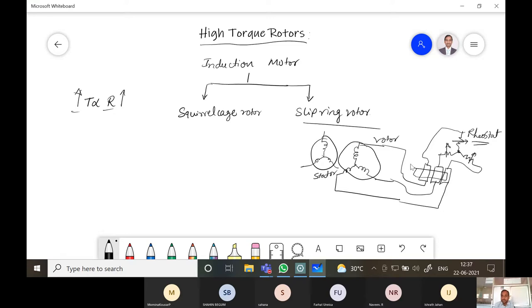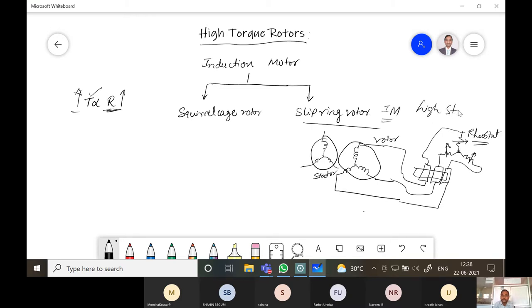During starting, the rheostat is connected; at the time of running, the rheostat will be disconnected and the rotor runs under normal condition. We can vary the resistance of the rotor by inserting some external resistance into the circuit. The slip ring induction motor has a high starting torque because it has high resistance during starting.